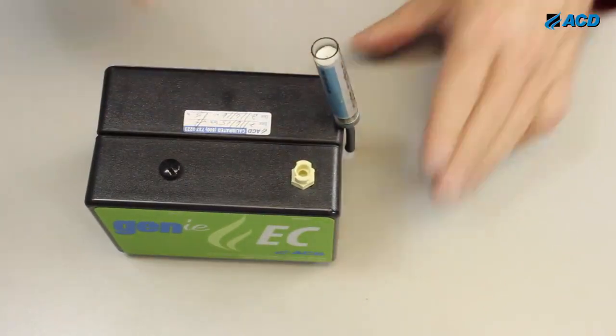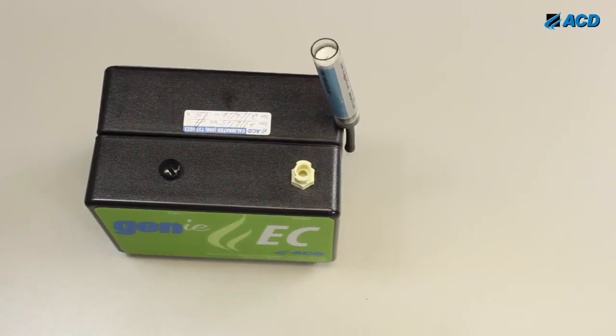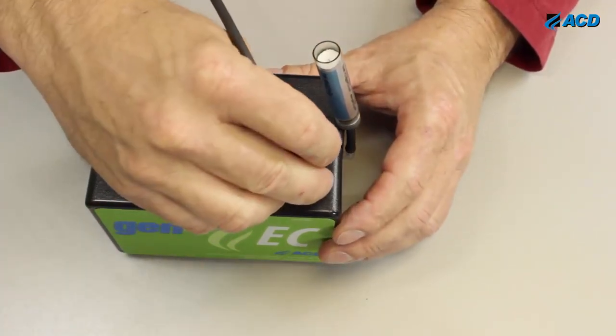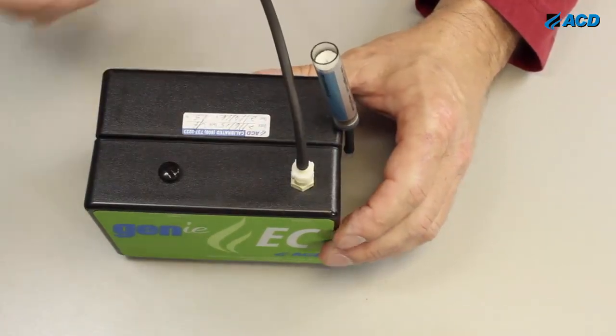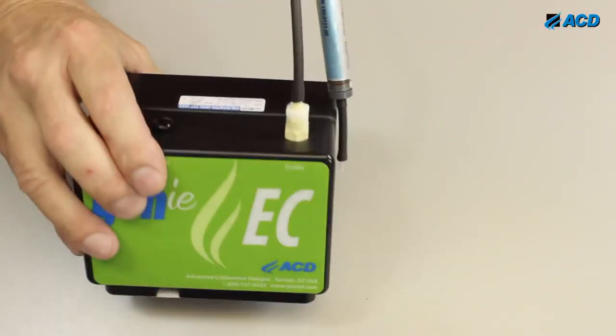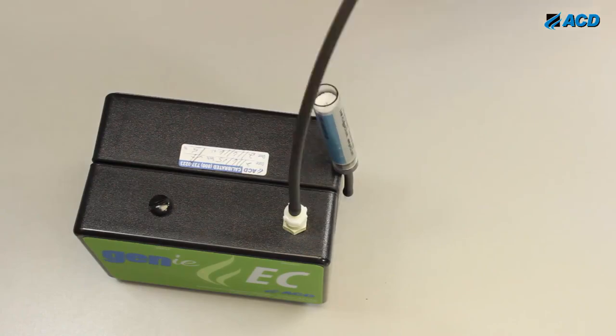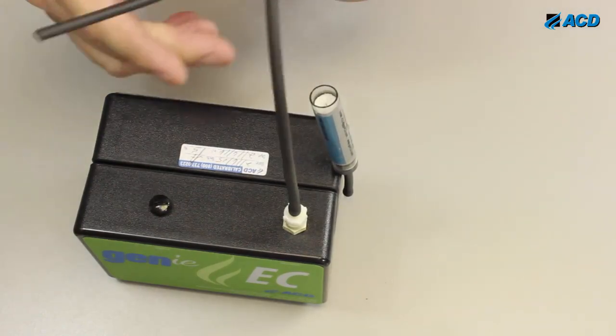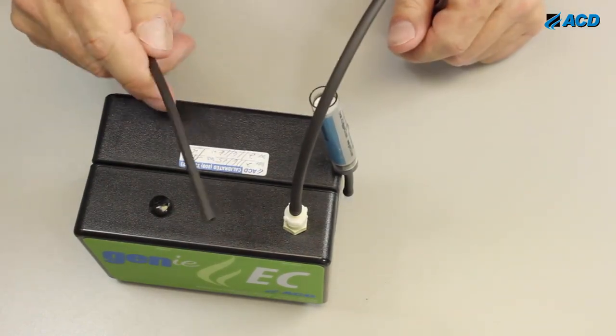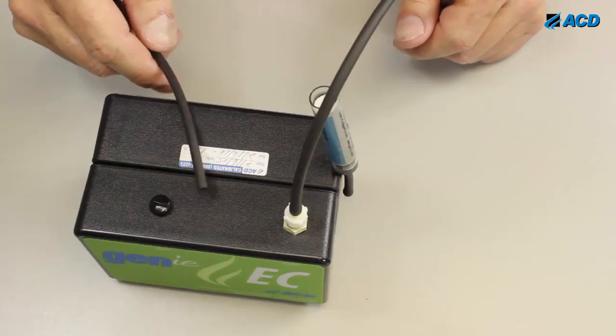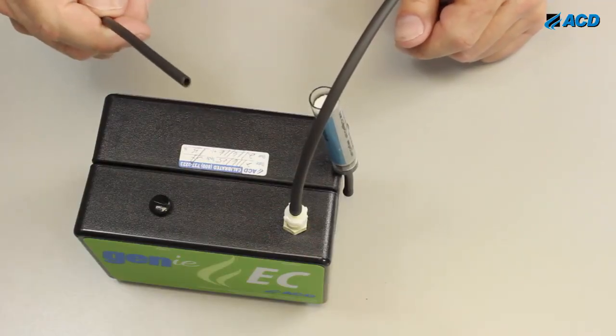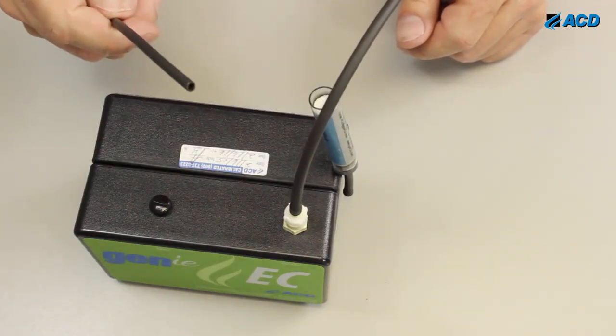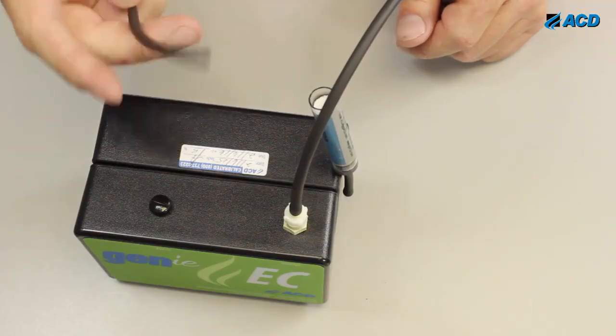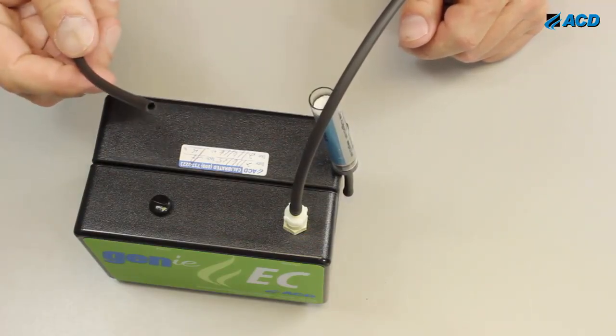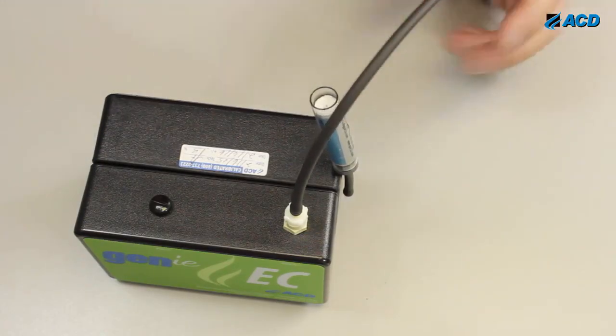Here's the outlet of the calibration gas, so that's where your chlorine gas in this case comes out. It comes with a 5-foot hose with a quick connect fitting like that, so that's connected to the top of the unit. And then the other end of this hose simply would have the calibration adapter for whatever manufacturer you have. If you have different manufacturers, you just plug in those calibration adapters to the end of this hose, and attach them to your sensors for calibration.